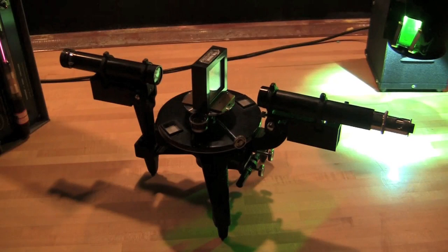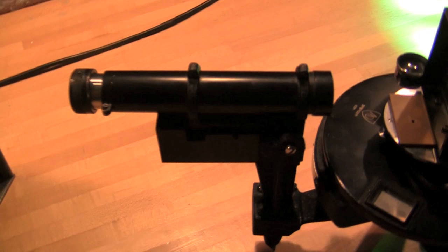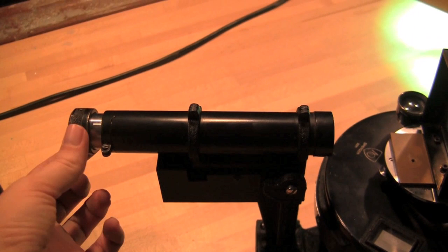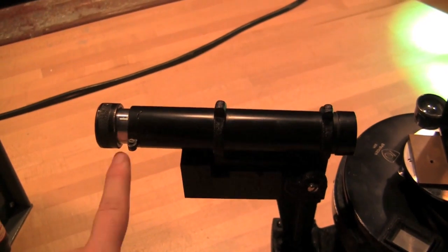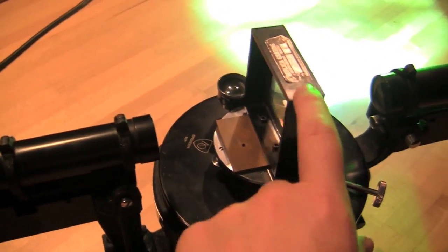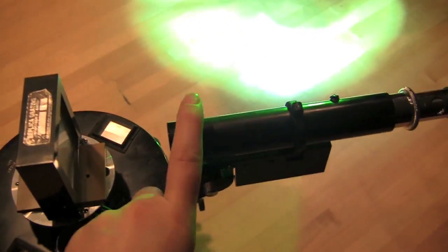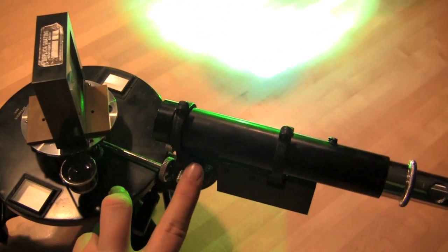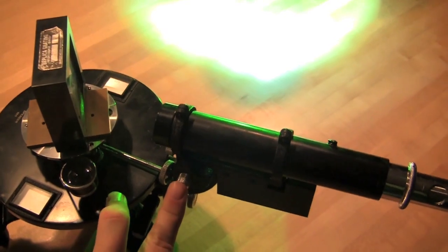Let's take a look at the spectrometer. On the input side is a collimating tube, which has an adjustable aperture so you can control the amount of light that gets through. The light that does get through the tube is collimated before it hits the diffraction grating. The grating is mounted perpendicular to the incoming light. Light diffracts from the grating and can be viewed again by a telescope. The angle between the telescope and the collimating tube is indicated on the platform of the spectrometer. Before we trust these angle measurements, we'll have to calibrate the spectrometer.